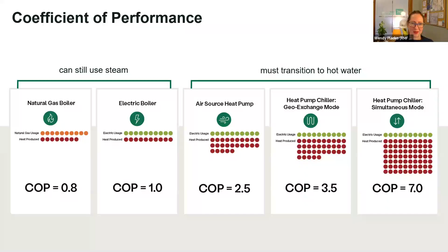This is kind of the cheat sheet for how you relate electrical into all these large campus decarb plans. Just a couple of numbers to give you scale: if you are replacing a 100,000 pounds per hour steam boiler with an electric boiler, you just added 30 megawatts to your campus. If you do it with an air source heat pump, you end up with a 15 megawatt increase instead, because of that relationship. And if you go geo exchange, ground source, water source, you limit it even more. In this case, we use a conservative COP of 3.5 to get down to 8.5 megawatts.